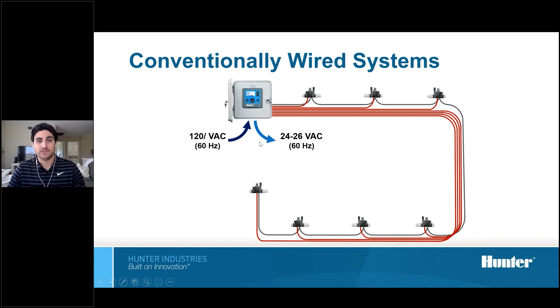Every single valve or valve box potentially has a big bundle of cable going through there, all throughout an entire project, all the way out to your last zone. Typically in a United States installation, we have 120 volts coming in at 60 hertz frequency. Internationally, you typically see 230 volts at 50 hertz. So that's the power coming into the controller. And then out on the actual wire paths, we have 24 to 26, sometimes 19 to upwards of 27, 28 volts AC on those wire paths going out to your valves to actuate those solenoids. Everything stays consistent with the frequency. If we're in the US, we have 60 hertz coming in and 60 hertz going out. If we're international, we have 50 hertz coming in and 50 hertz going out. It's very straightforward, very fault tolerant, easy to troubleshoot. 24 volts, 60 hertz is pretty straightforward for any conventionally wired system.